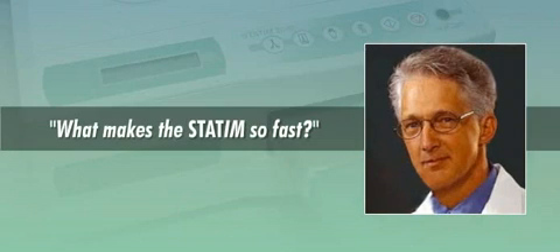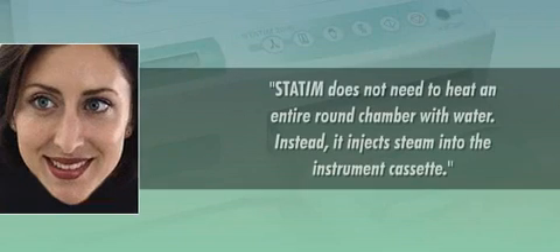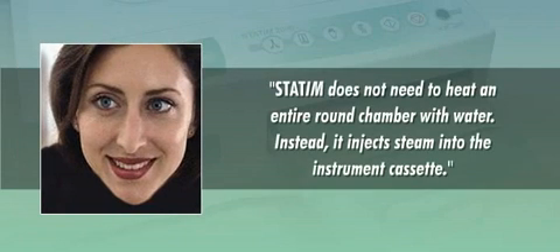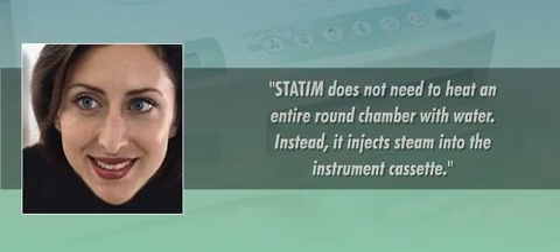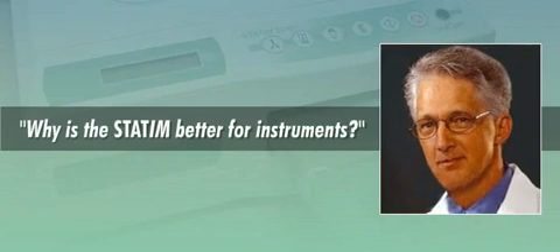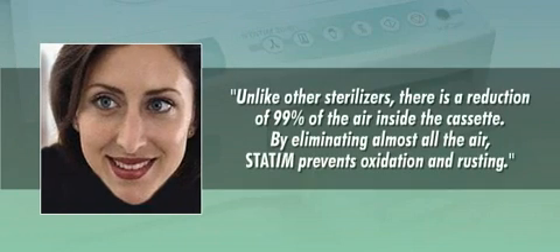What makes the STATIM so fast? STATIM does not need to heat an entire round chamber with water. Instead, it injects steam into the instrument cassette. Why is the STATIM better for instruments? Unlike other sterilizers, there is a reduction of 99% of the air inside the cassette. By eliminating almost all the air, STATIM prevents oxidation and rusting.